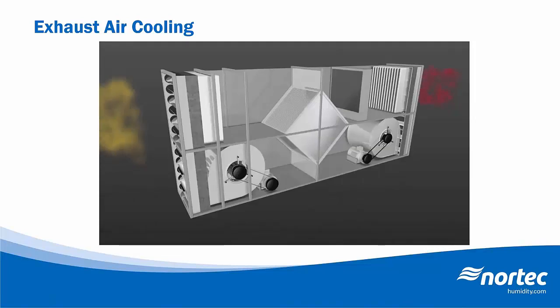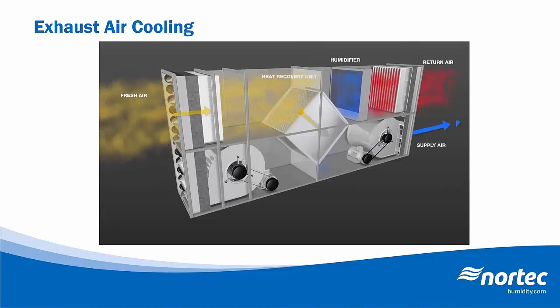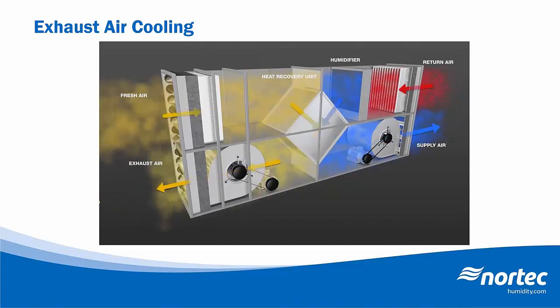The third strategy that we'll look at is exhaust air cooling. So this strategy uses the exhaust air in combination with the heat recovery unit to effectively pre-treat the supply air prior to it being introduced into the room. So when air is extracted from the room, it's typically warmer than the incoming air and not really suitable for use in cooling. But by humidifying the exhaust air with an evaporative cooler and reducing its temperature below that of the incoming air, we can run it through the heat recovery unit and cool the incoming supply air.